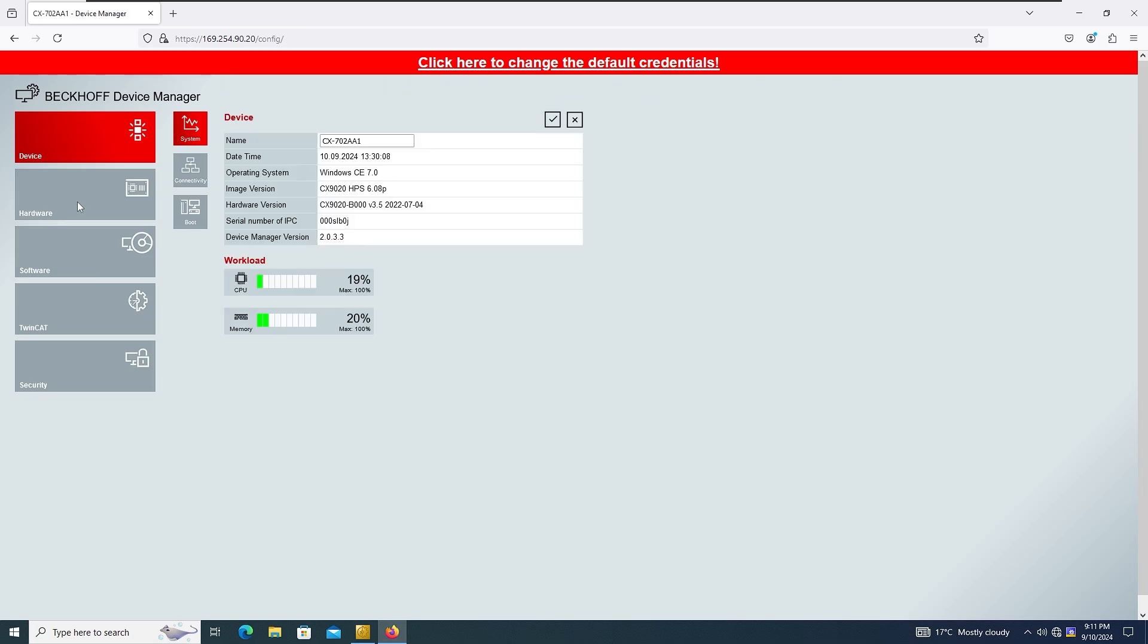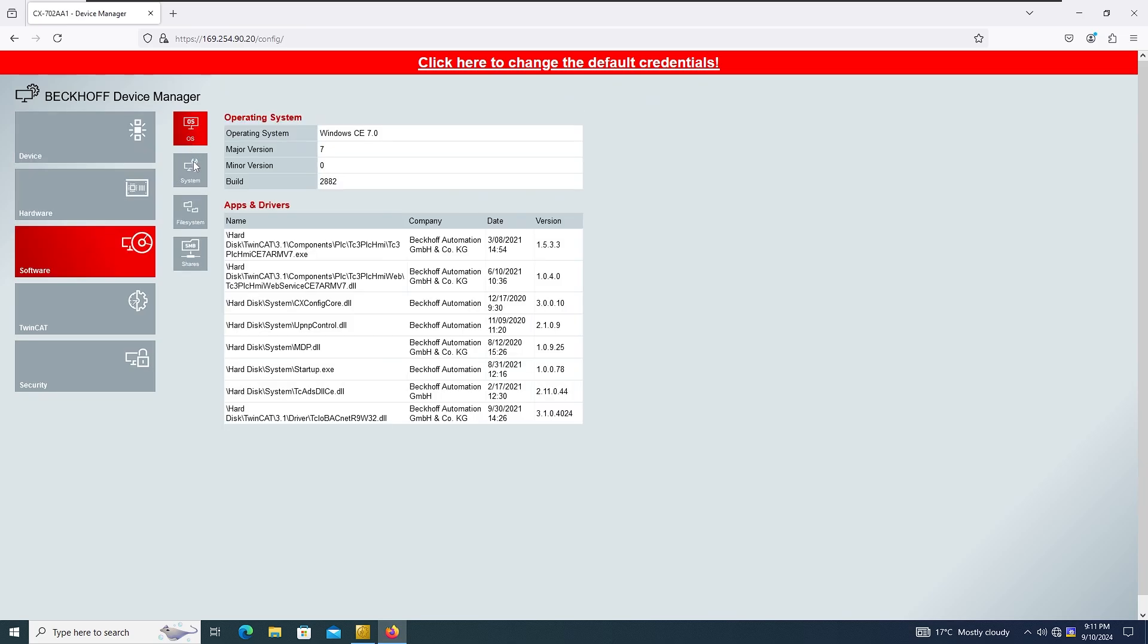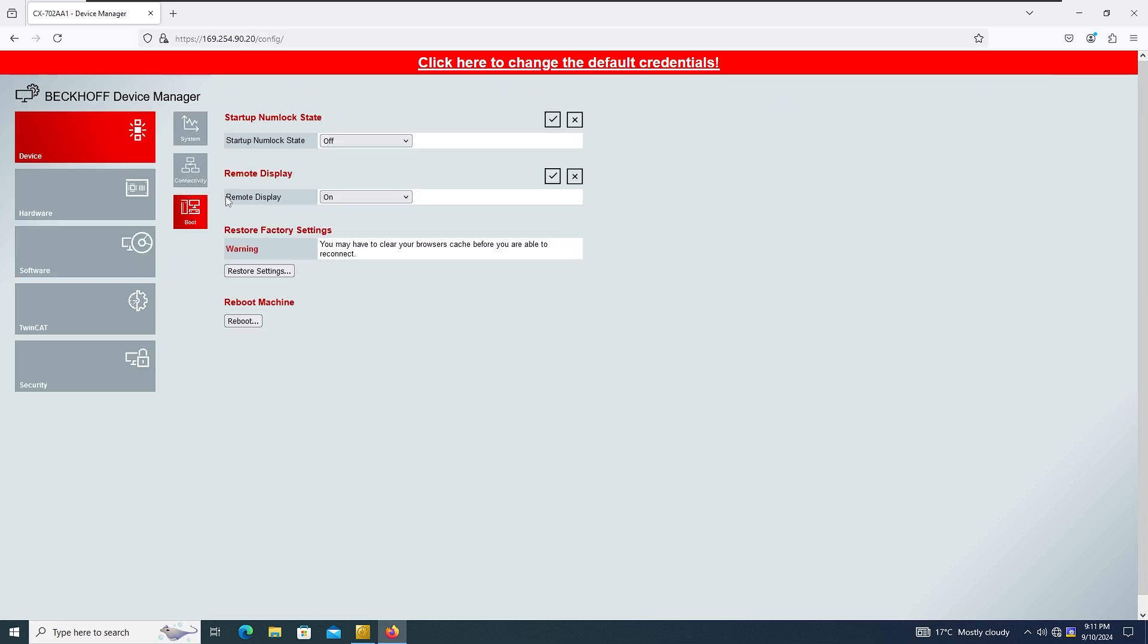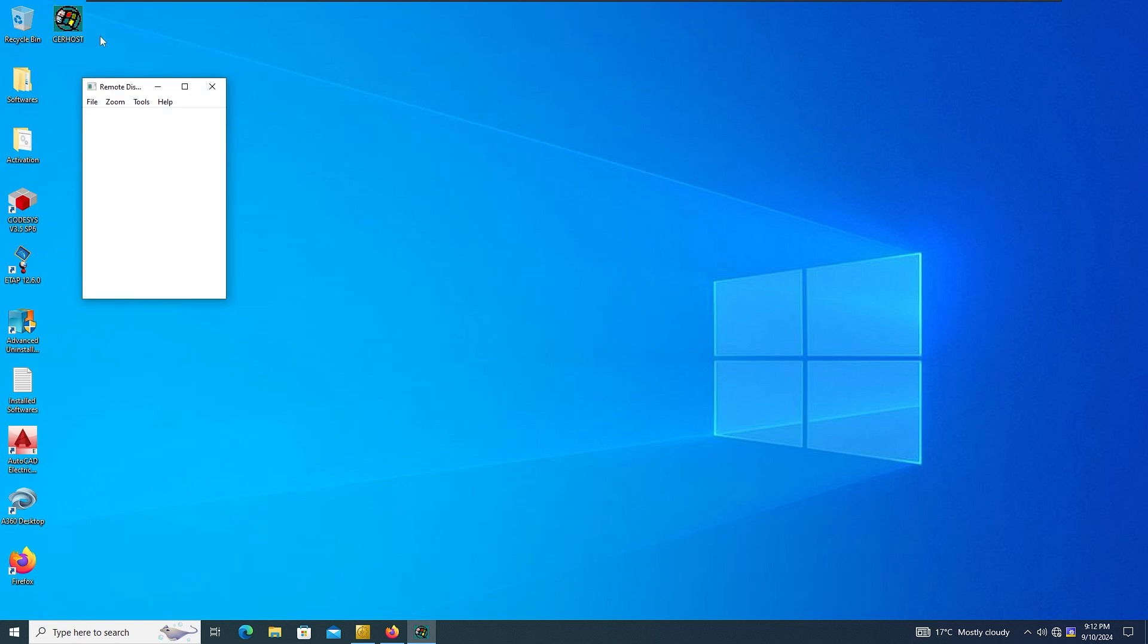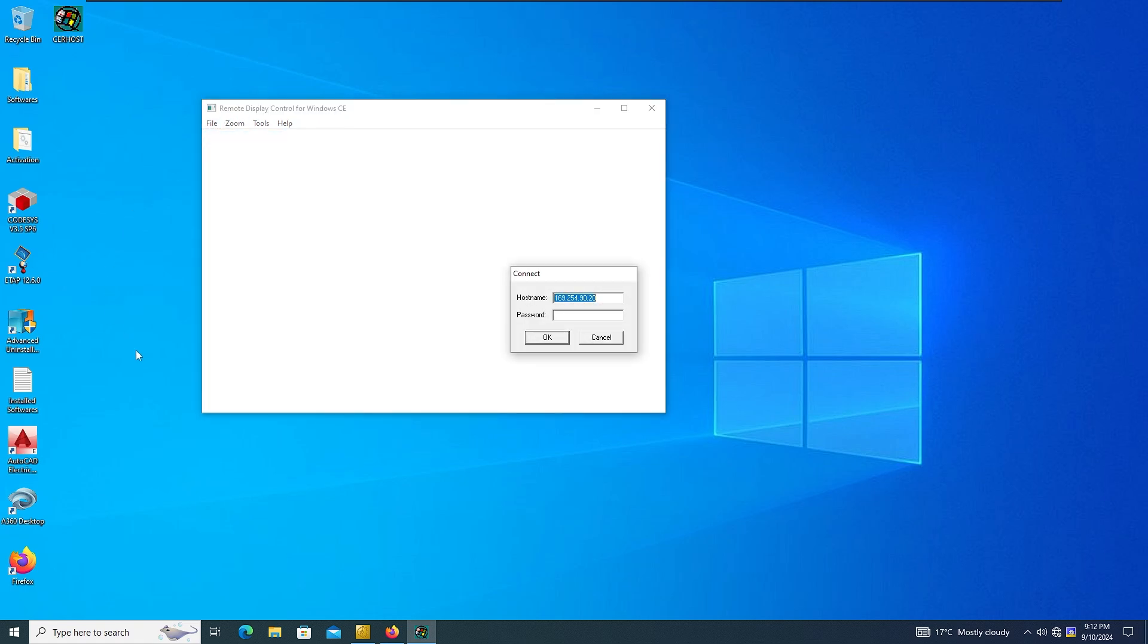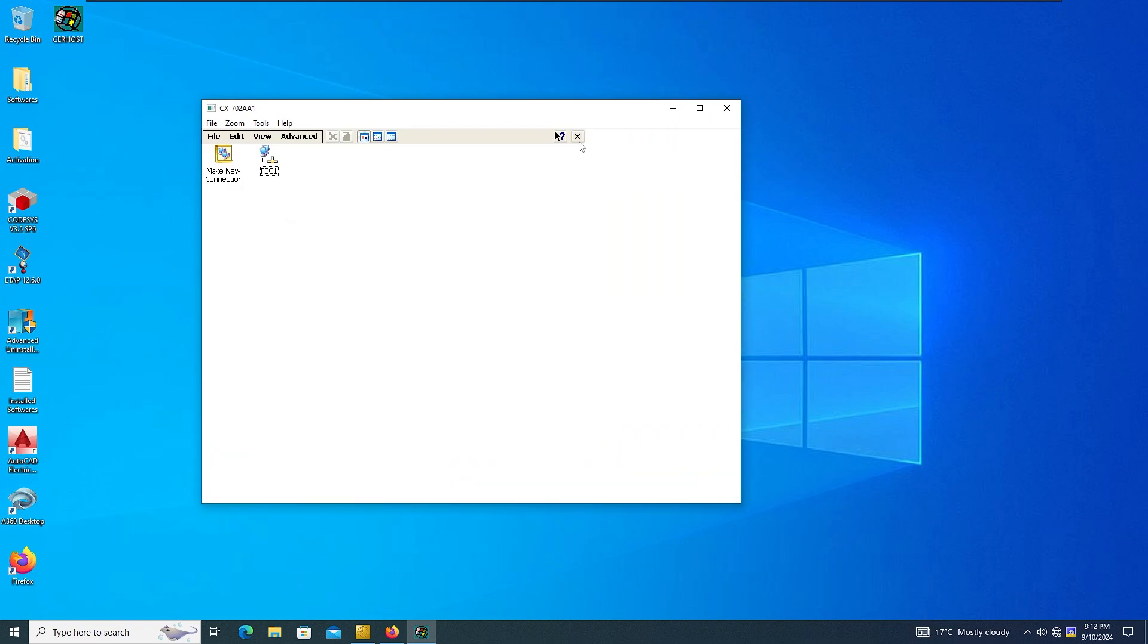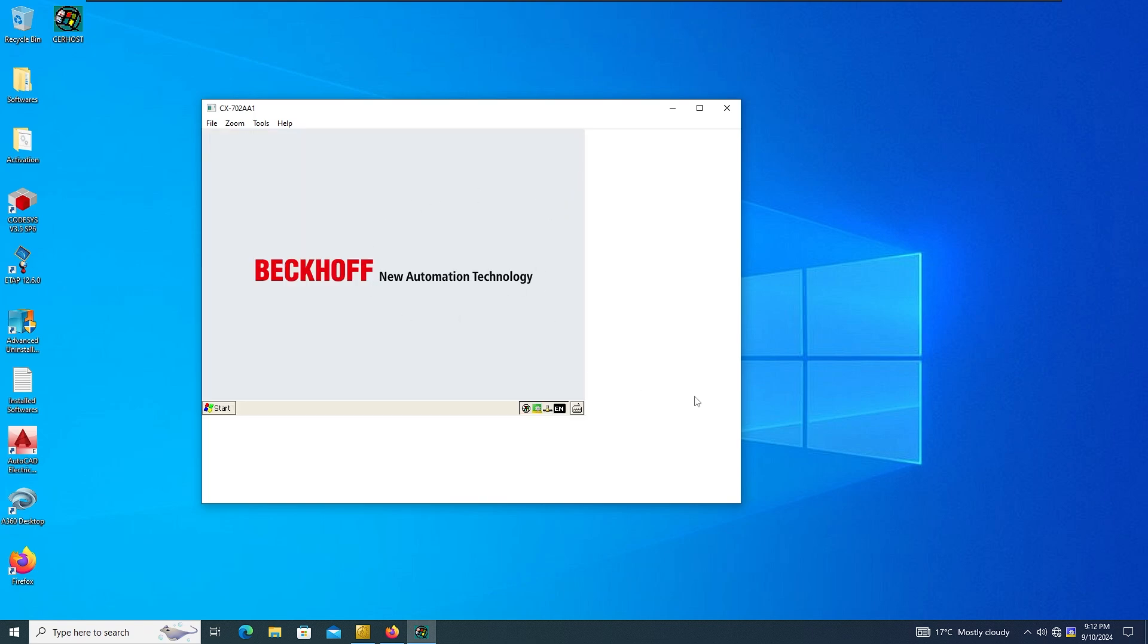You can go to the Windows that is installed on the machine. If this remote display is on, then you will be able to use this software called CERHost. You can download this one from the Beckhoff website. It's just an executable file in a zip file. What I do is get connected in here. You can write the IP address of the PLC and it's going to get connected to it. I opened these on the previous side. That's the Windows that is installed on the PLC.